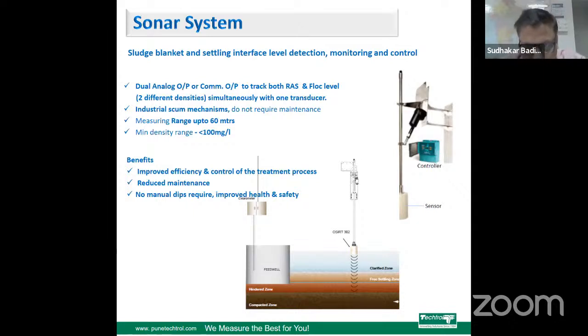two different types of specific gravity liquids, or you can say the sludge or the solid particles. Basically, this is used to measure the sludge level detection under the water. Then that output, the sludge detection or monitoring, is used for the further control of the clarifiers.